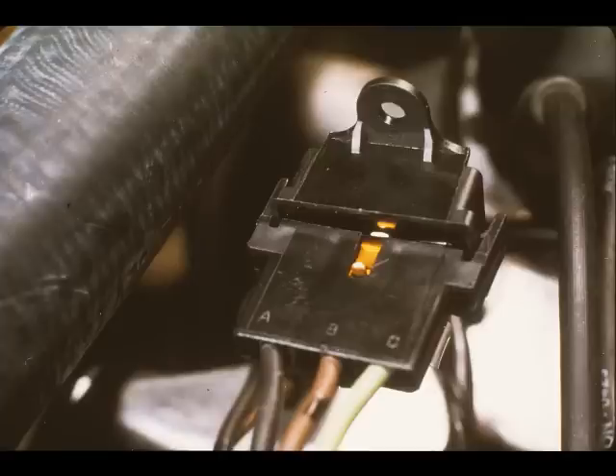If the pressure or temperature inside the compressor rise above a critical level for a prolonged period, the superheat switch will disengage the compressor clutch by shorting its power supply to earth, causing this thermal limiter to blow. Although the same temperature and pressure levels may occur during normal operation, their duration is not sufficient to cause the unit to blow.